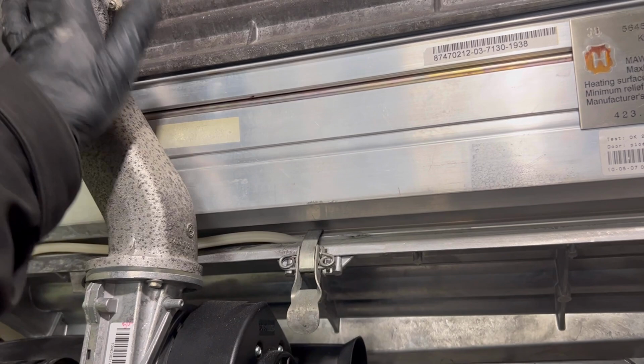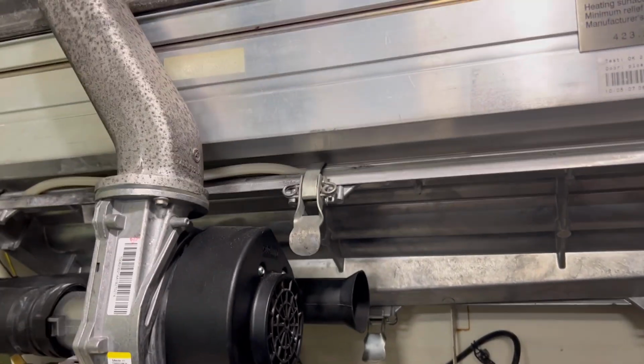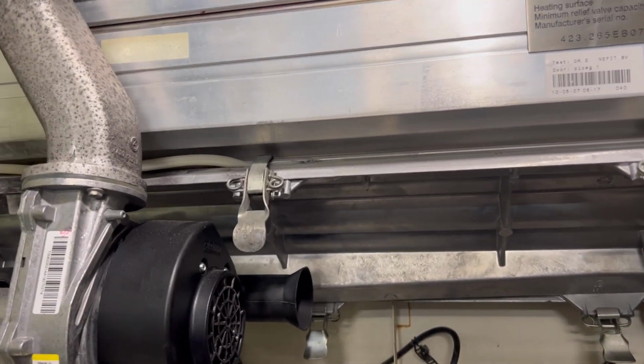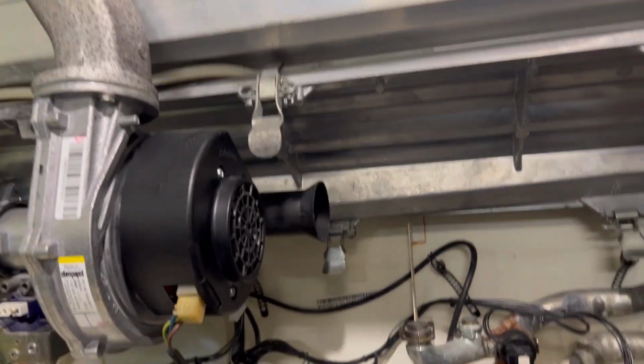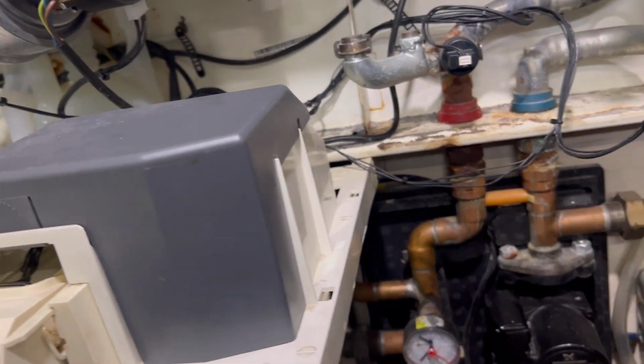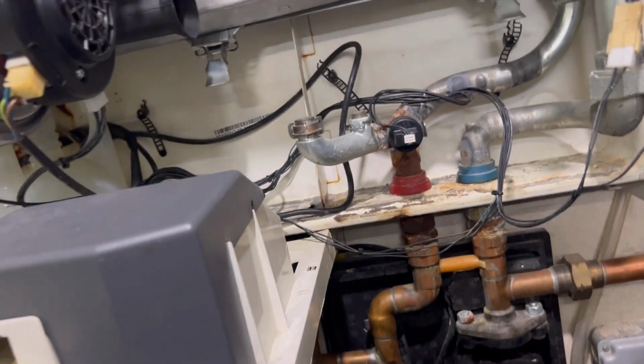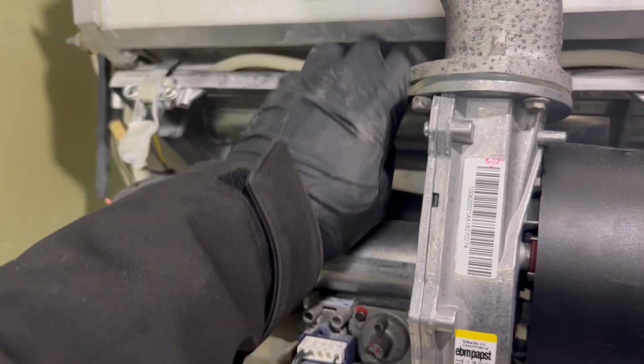There's gotta be the correct separation between the exhaust here and the fresh air intake. So this boiler sucks in fresh air from the outside for proper combustion. Like if we put elbows on those two pipes. I don't want to say some of the damage was already done, because all of this rust and corrosion here, that's basically where it's stemming from. I don't know, this gasket, this seal here, I'm going to show them also.